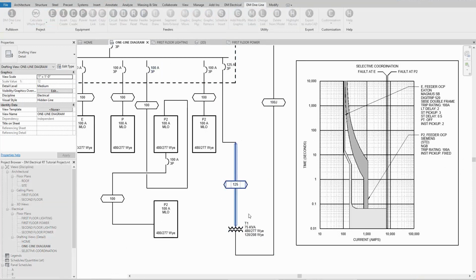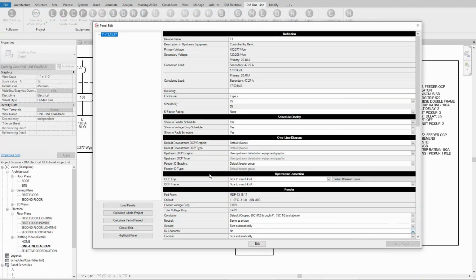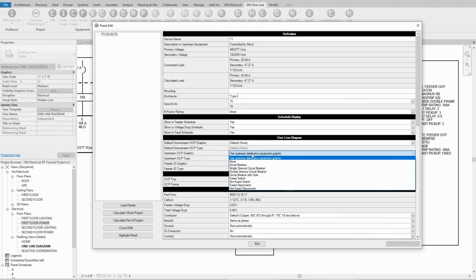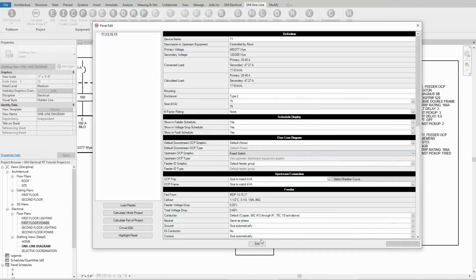When we modify this device, in the one-line diagram we're actually specifying what breaker type graphic to use for it. Its overcurrent protection is using a default, basically saying I want to use whatever is the upstream device. I can specify what breaker, but I can say, actually I want a fused switch here. I can change it here for this transformer, and it'll update it on the one-line automatically.